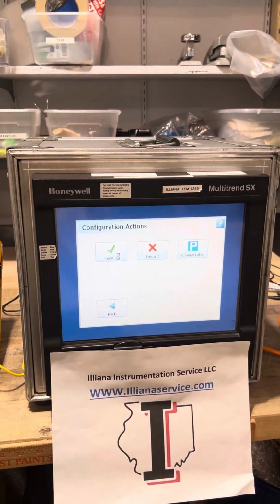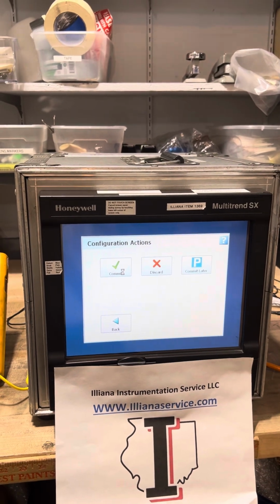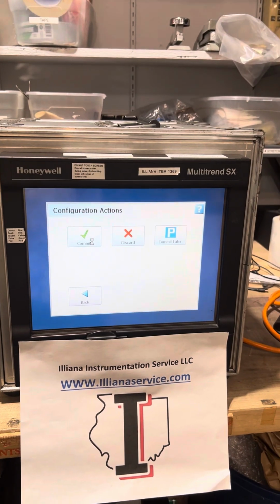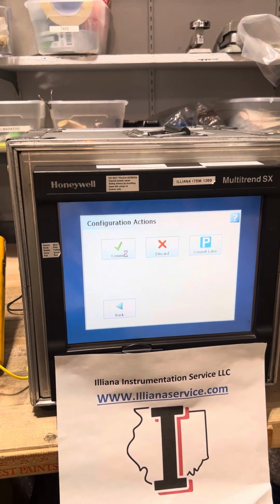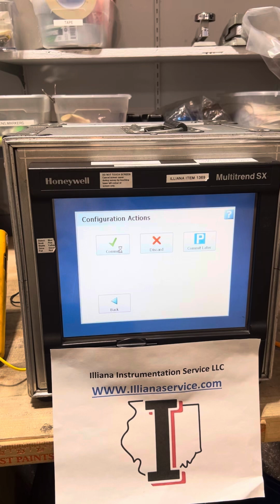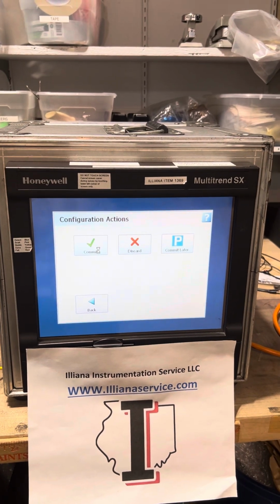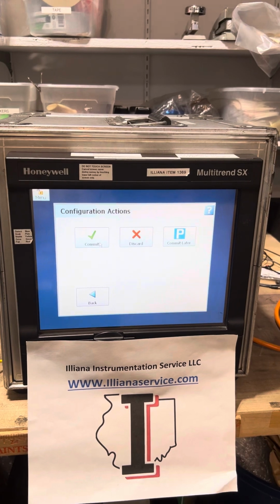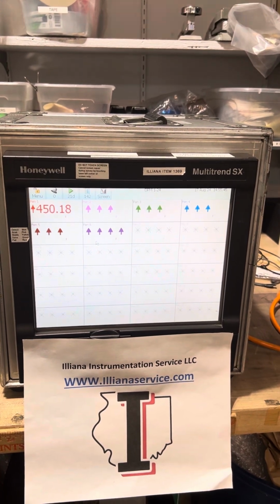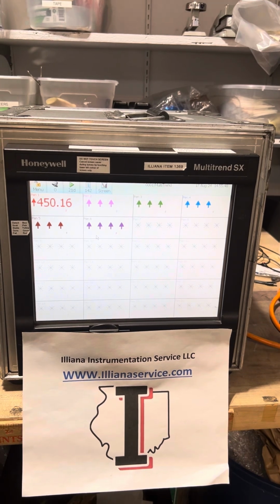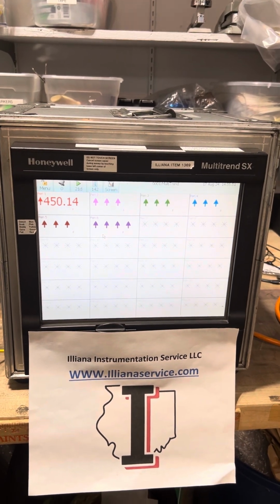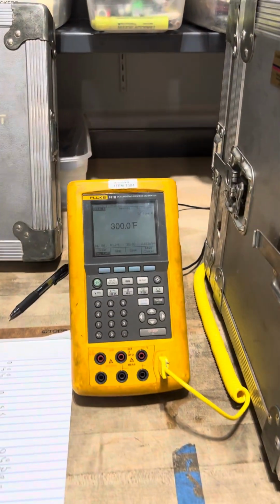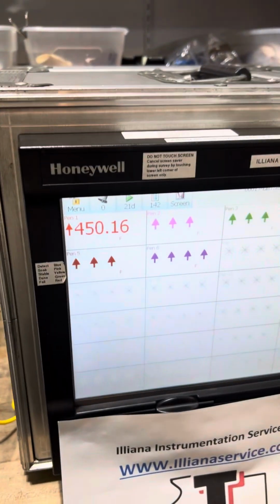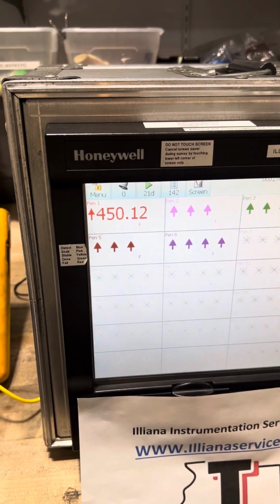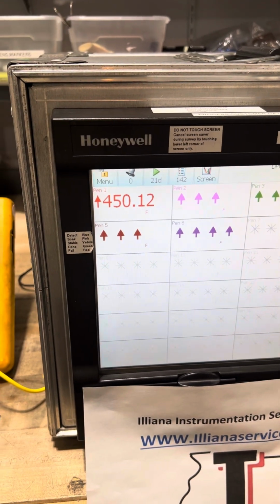The one correction, the multi-point correction, was put in there to actually calibrate the recorder properly. That second value that I put in there was to correct for the fact that the thermocouple wire was not perfect. And if you'll recall, I had put in a 100-degree offset to correct the recorder calibration, and then I put in a 50 for the wire. So now my Fluke calibrator is set at 300, and I'm reading 450, and that 450 was derived from 100 put in there for recorder correction, and the 50 for the wire correction.